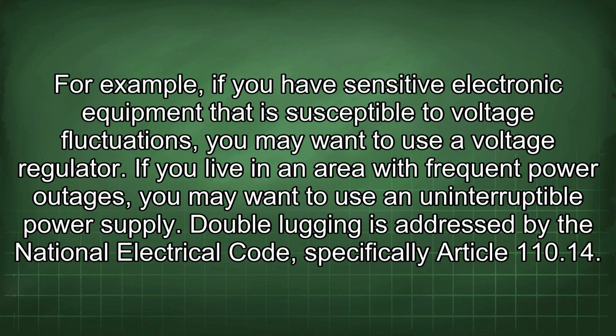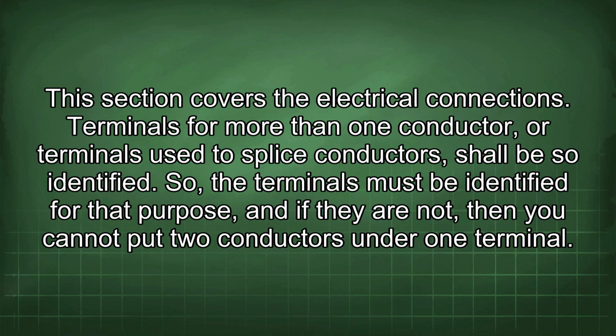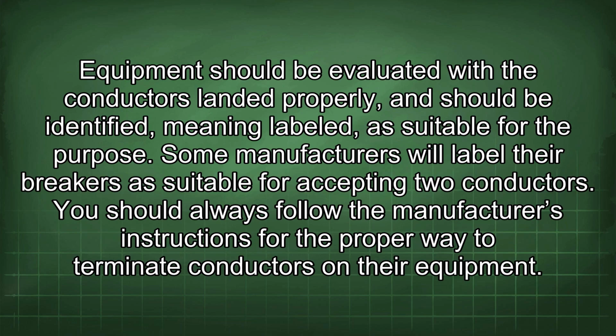Double lugging is addressed by the National Electrical Code, specifically Article 110.14. This section covers the electrical connections. Terminals for more than one conductor, or terminals used to splice conductors, shall be so identified. So, the terminals must be identified for that purpose, and if they are not, then you cannot put two conductors under one terminal. Equipment should be evaluated with the conductors landed properly, and should be identified, meaning labeled, as suitable for the purpose. Some manufacturers will label their breakers as suitable for accepting two conductors.